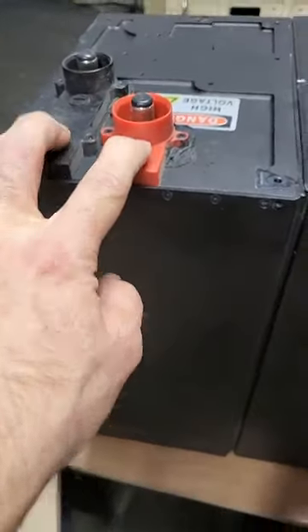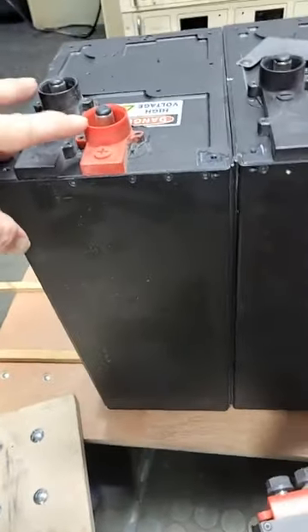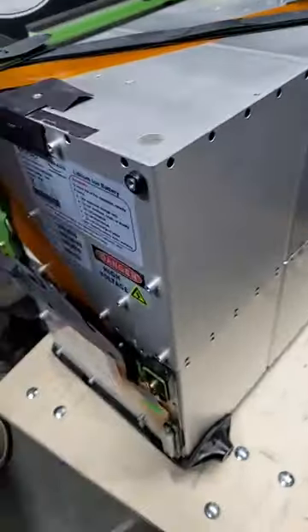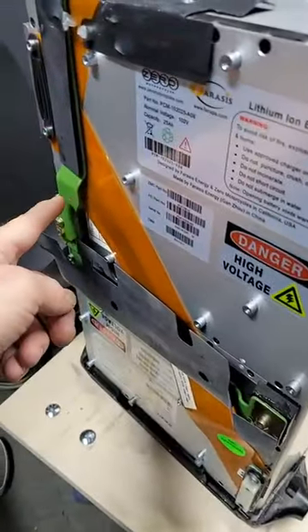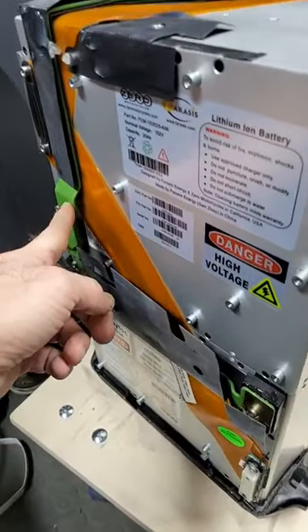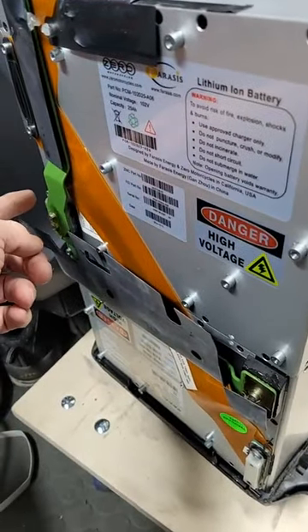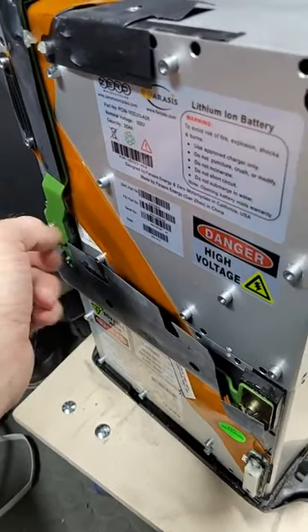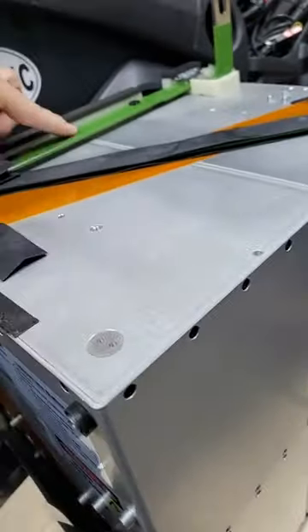As you can see, these are connected quite differently. You have big posts here, so this is about 110 volt DC here. On these modules, these are the bus bars made of copper, nickel plated copper, and there's a ceramic coating on top of these, so these are not conductive.